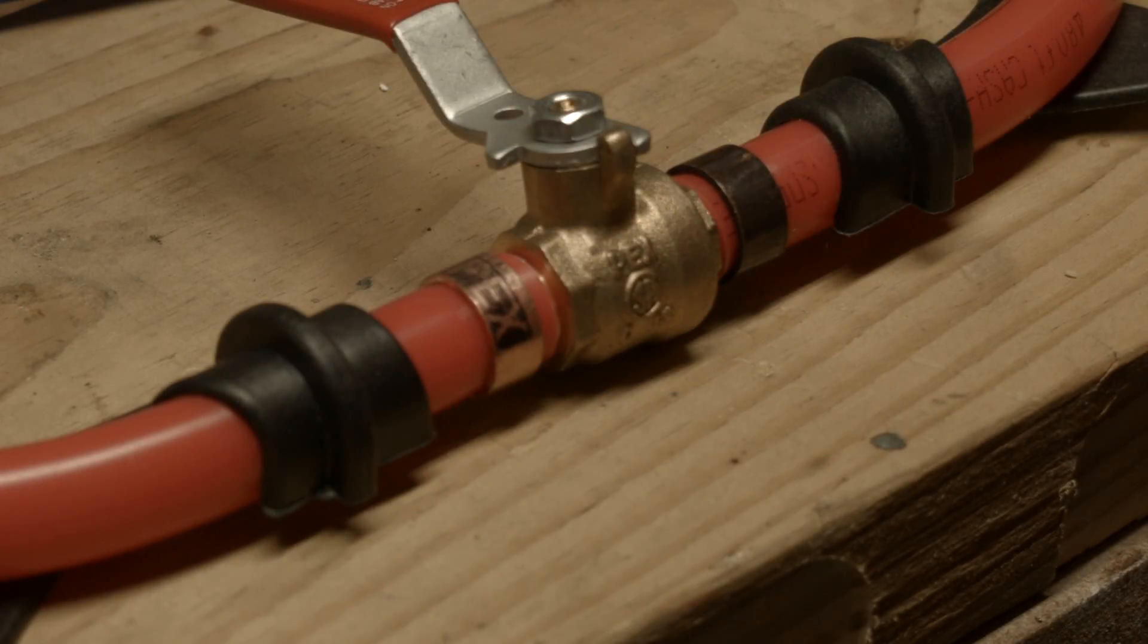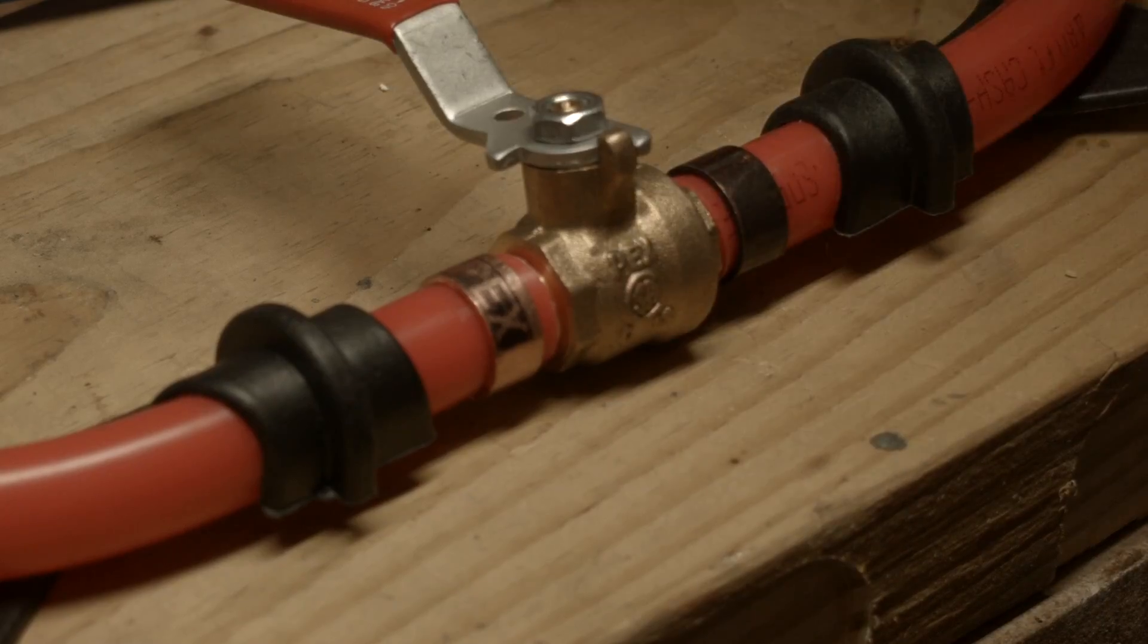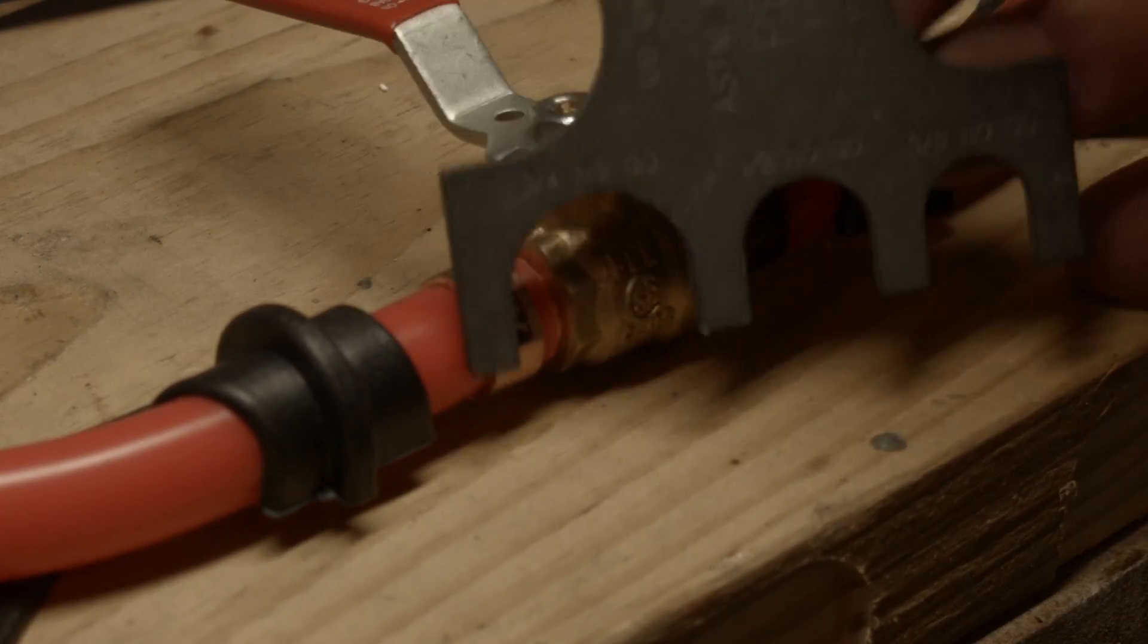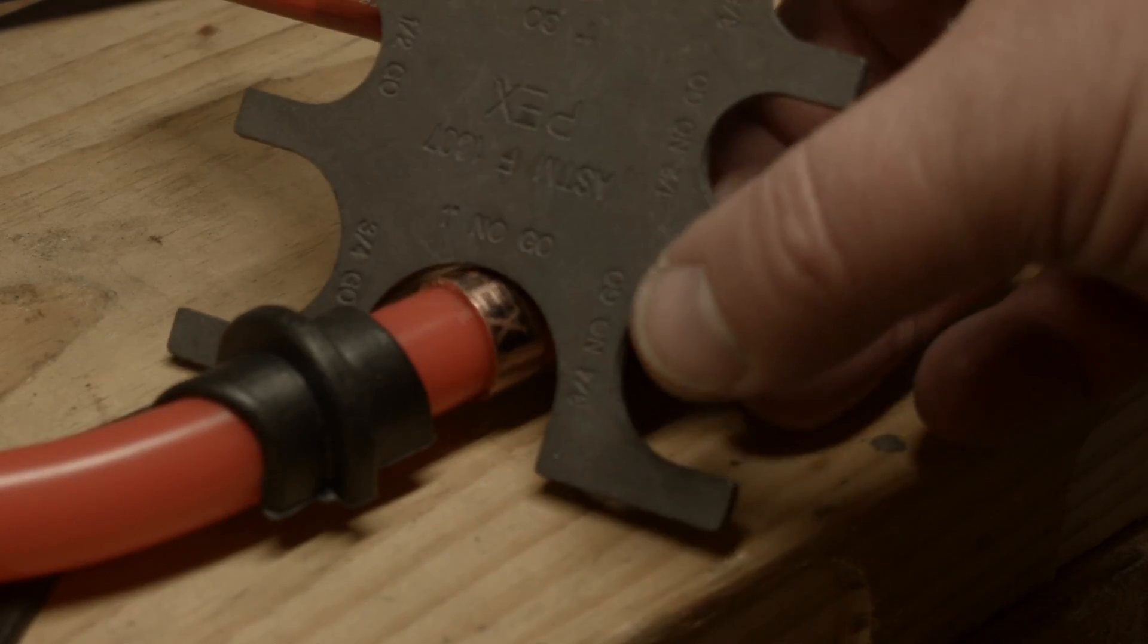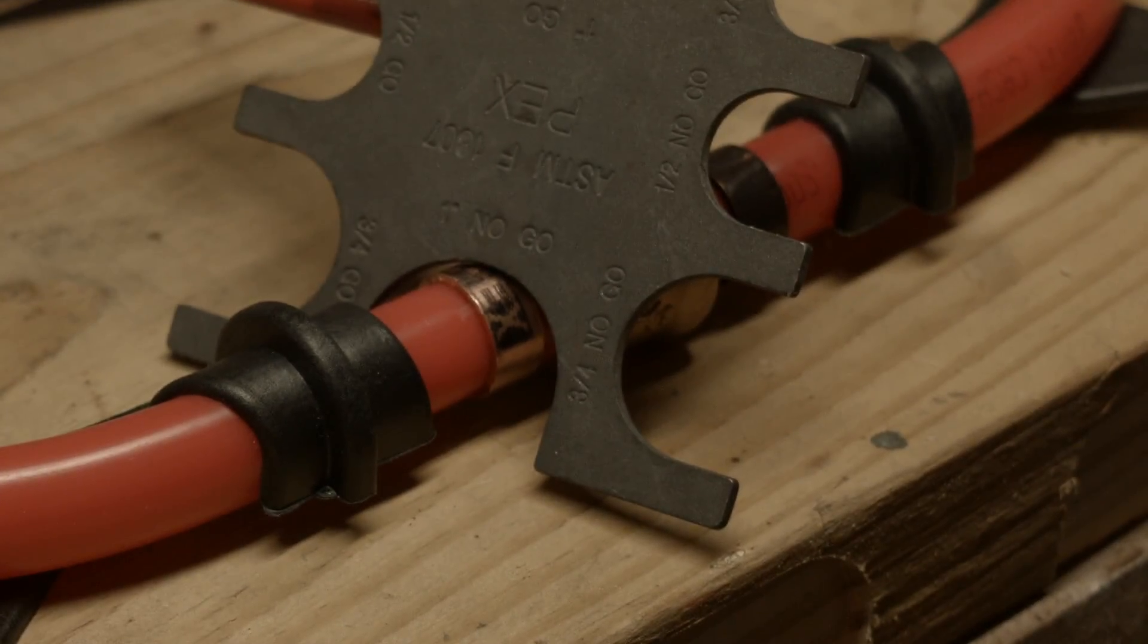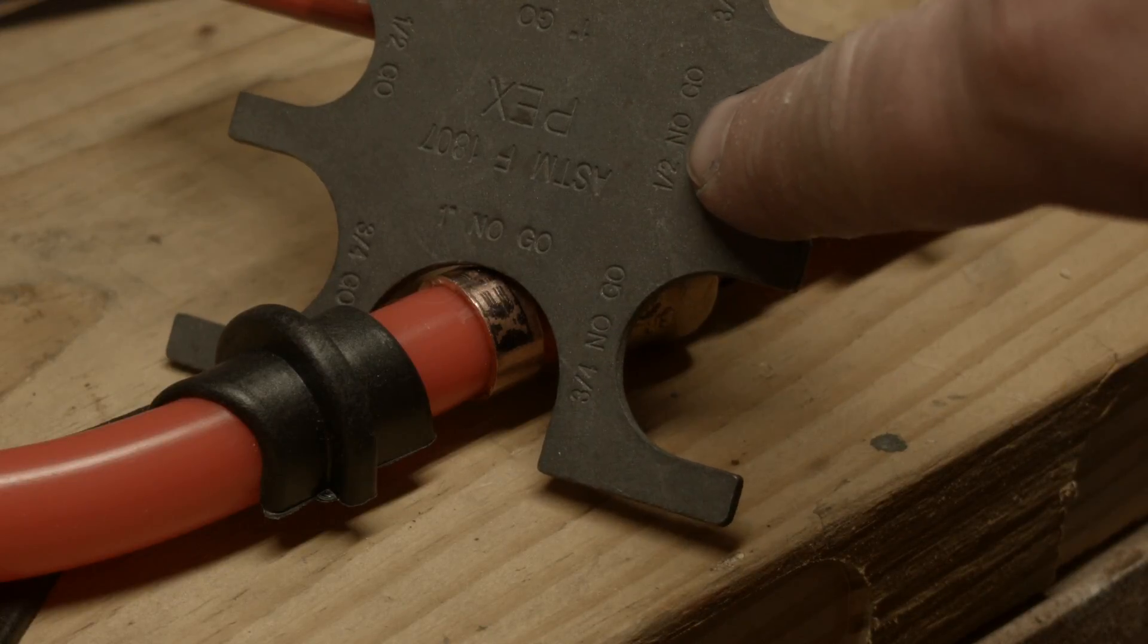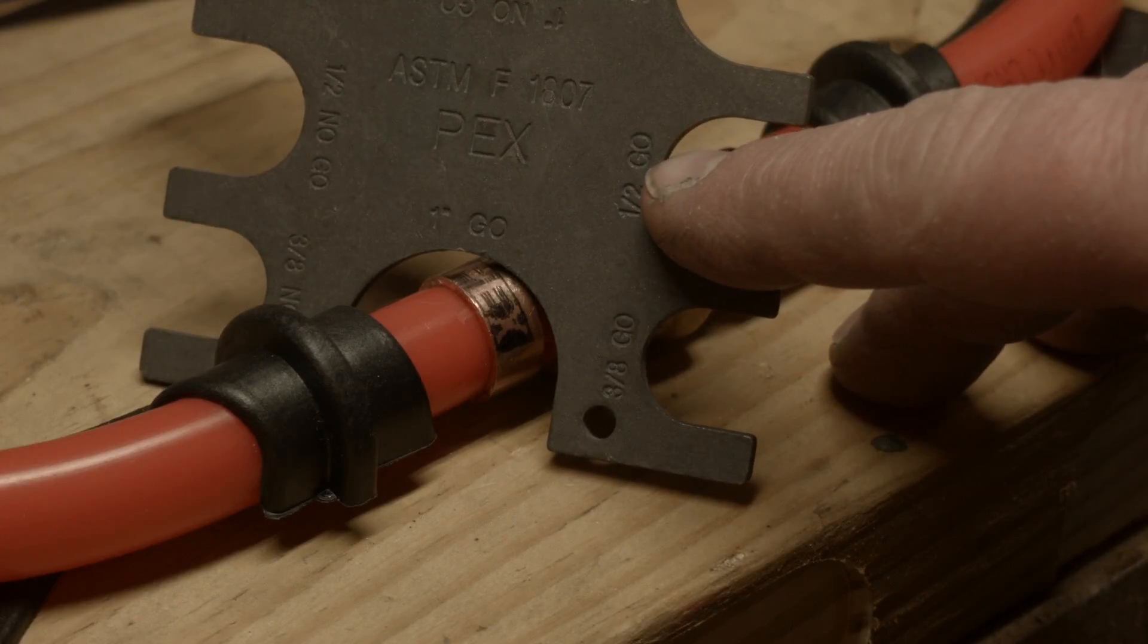To make sure the compression is successful, you use a gauge. The gauge has markings on it. For a half-inch pipe, it's the center one. There's one that says no-go—here, half-inch no-go. And on the other side is half-inch go. There it is.